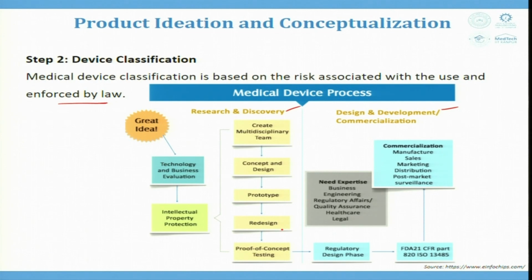How do we create the team for medical design and how do we try to concept and design, prototype, redesign, proof of concept. This is taken from a reference, and here you can see the FDA 21 CFR 820, ISO 13485 compliances are given, which are to be taken care of when we are trying to work upon the design and development of the medical device or the commercialization of medical device in a different part of the world.